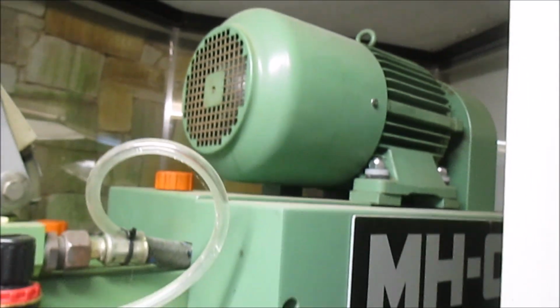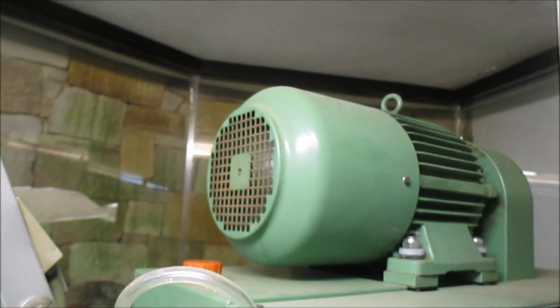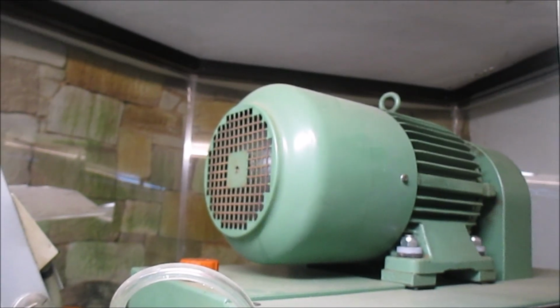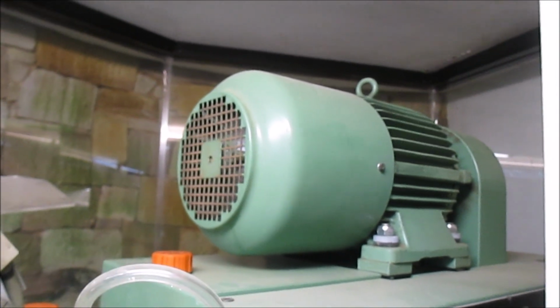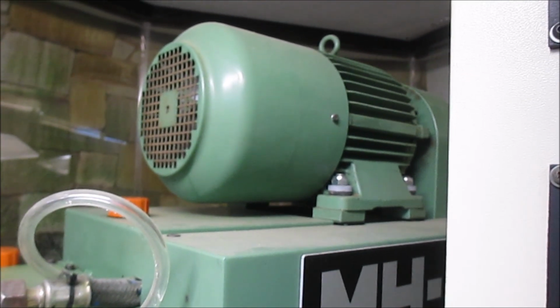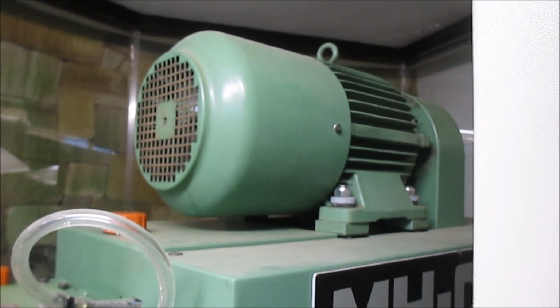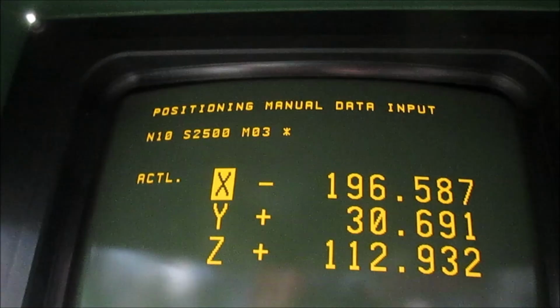So here's the motor changing, and the gearbox down here is changing. So you see it took quite a while. You might have heard it click over from star to delta. And that's that line there being executed.